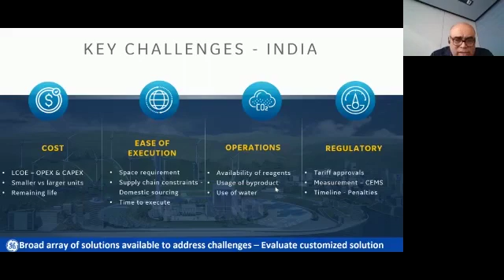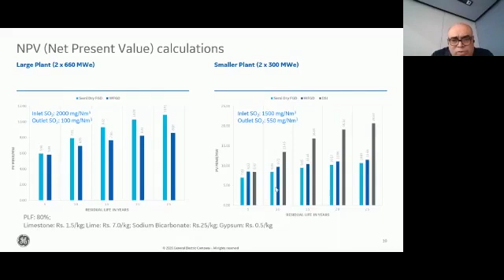And what we believe is that for a large power plant, say 600 megawatt or larger, or even 500 megawatt plus, the limestone FGD works out to be the preferred solution because it's the lowest in terms of overall cost. But when we are looking at smaller plants, typically in the order of 150 megawatt, 200 megawatt, or even 300 megawatt, with a residual life of say 10 years plus, we see that the semi-dry FGD, as we are talking about, with lime as the reagent, works out to be one of the most optimal solutions for the end user.